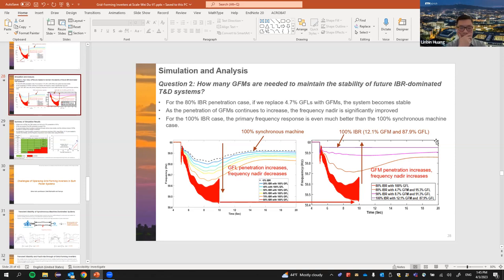And maybe another question: when you replace maybe one synchronous generator with maybe 200 inverters, and all of these inverters are operated in grid forming mode, would they be equivalent to one huge synchronous generator or one huge grid forming converter? Or is there something different? I think that depends on the scenario you are looking at, right? If you have one big power plant and you want a 300 megawatt grid forming inverter, in reality there are actually two megawatt inverters. You have 150 of them. They work in parallel, and then they become the 300 megawatt power plant.